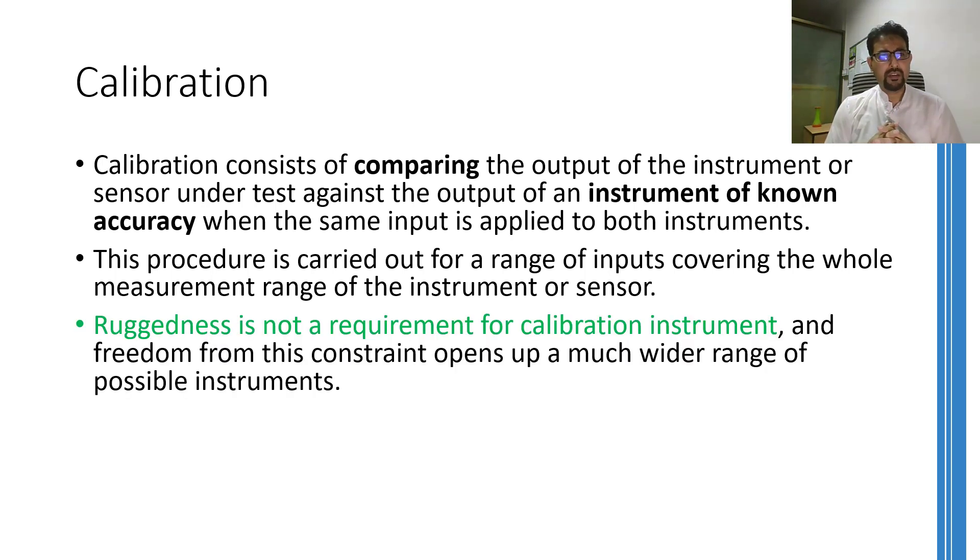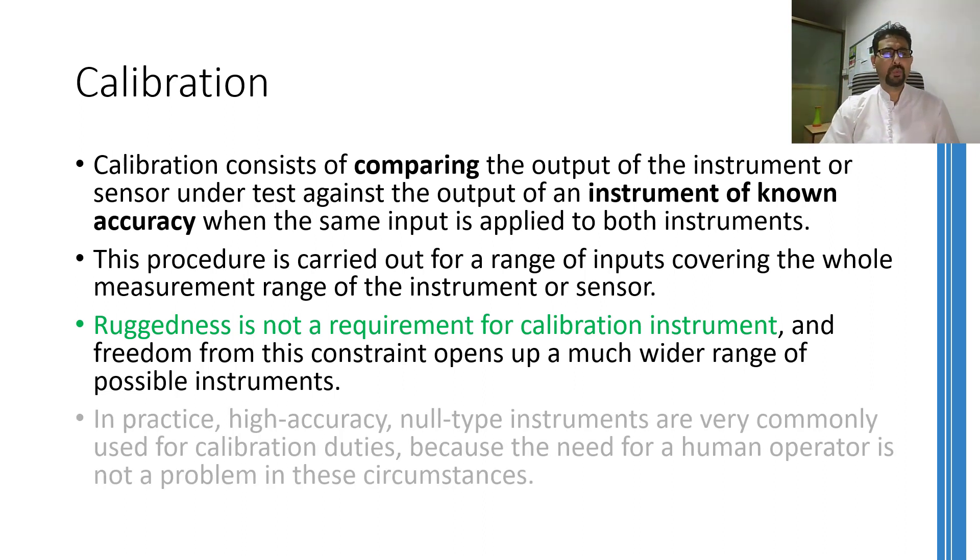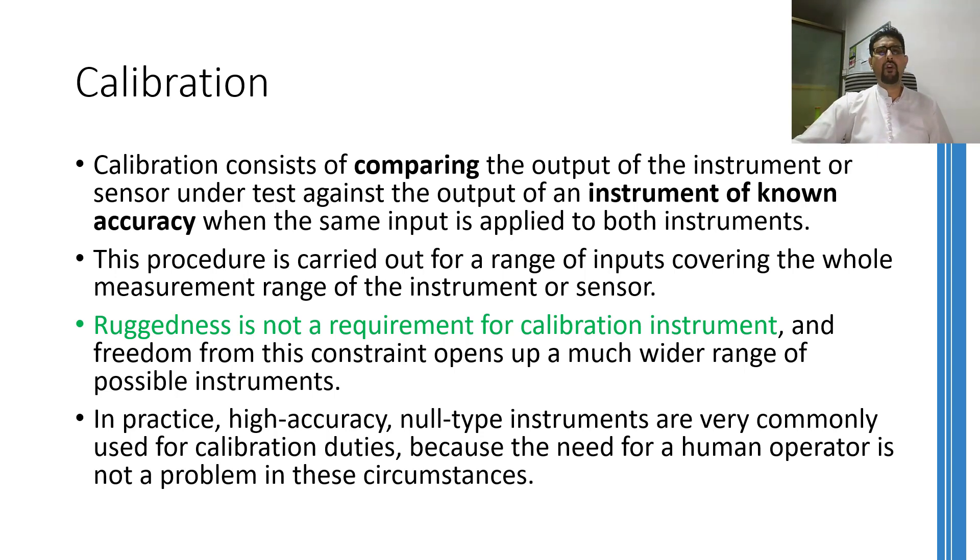If we talk about calibration instruments, that instrument must have an established accuracy. And as that instrument doesn't need to be operated in harsh environment and should only be kept in the lab environment in some controlled environment, therefore ruggedness is out of the list of requirements for this instrument. And you can well appreciate that if you remove this requirement, then it opens up a number of possibilities. We can have very good, very accurate sensitive equipment, which we know will never be used in any harsh environment. Therefore, in practice, high accuracy null type instruments are commonly used as calibration instruments. And as human involvement is not an issue over here, because you have to supervise the calibration process, the requirement of operating null type instrument by humans is not an issue now.